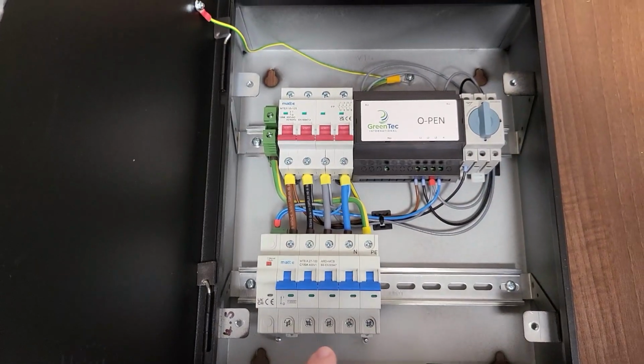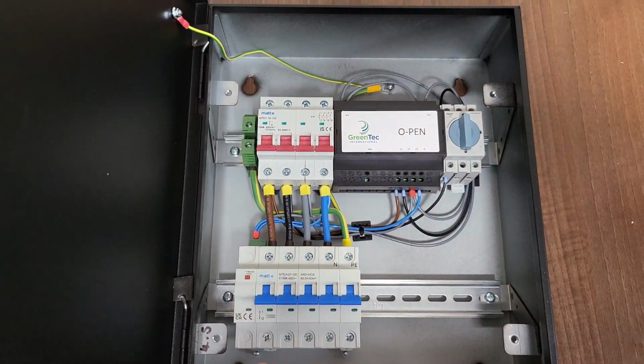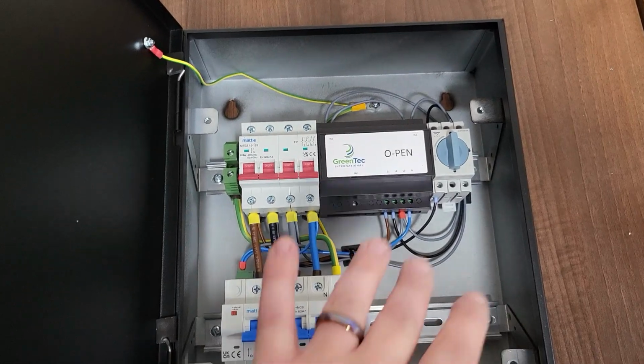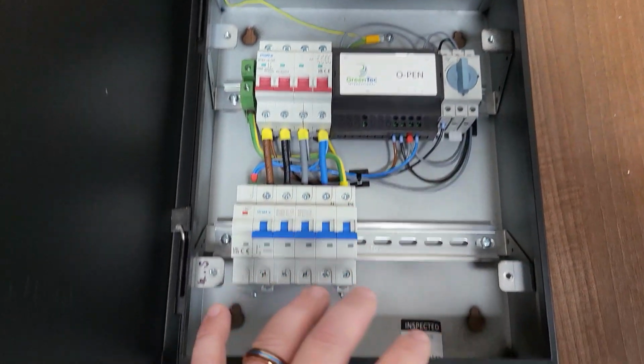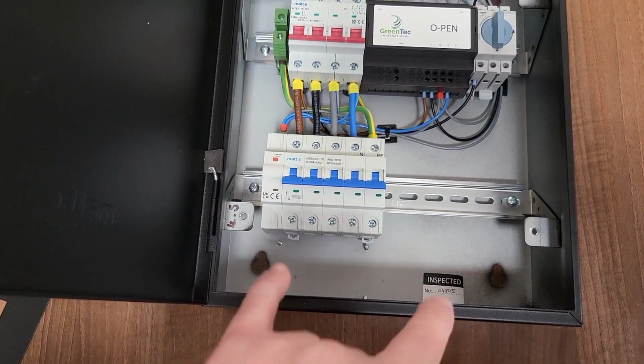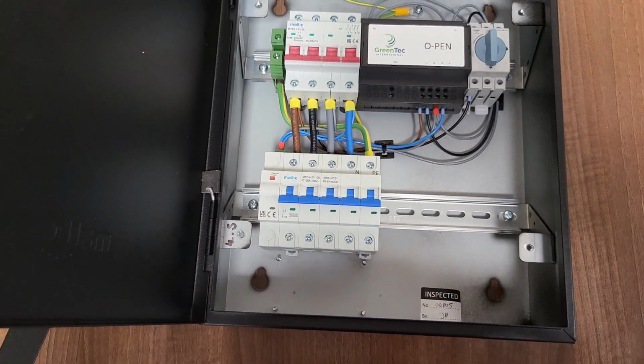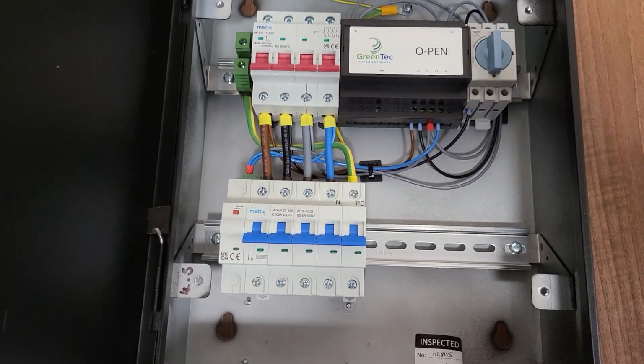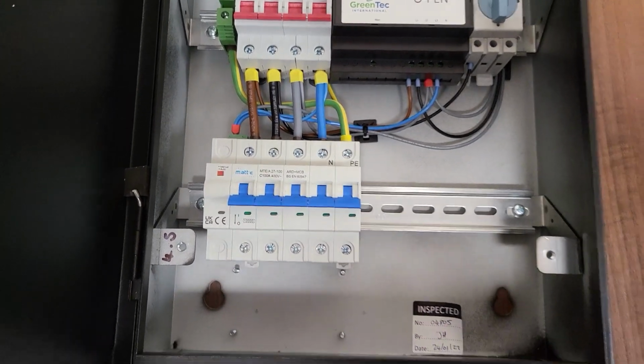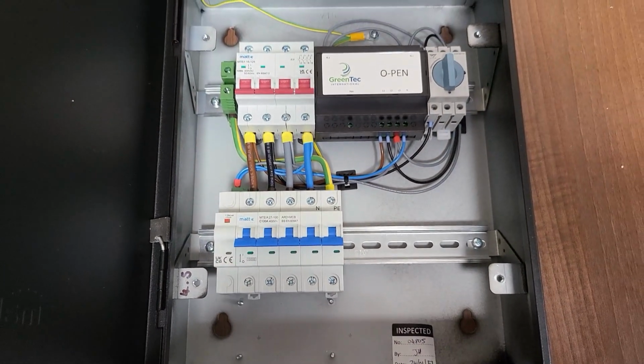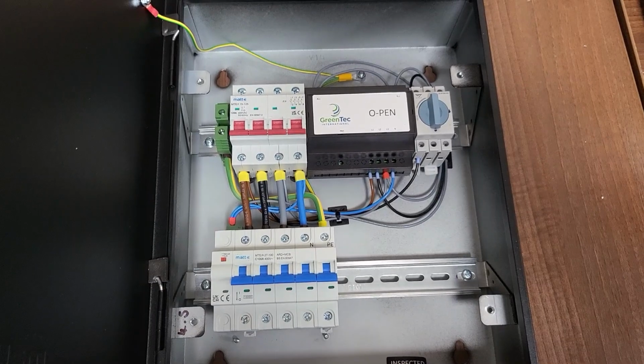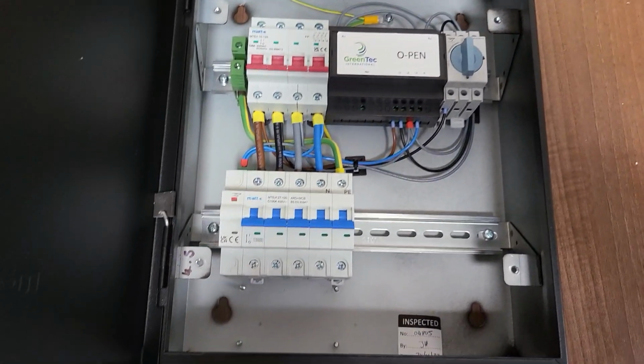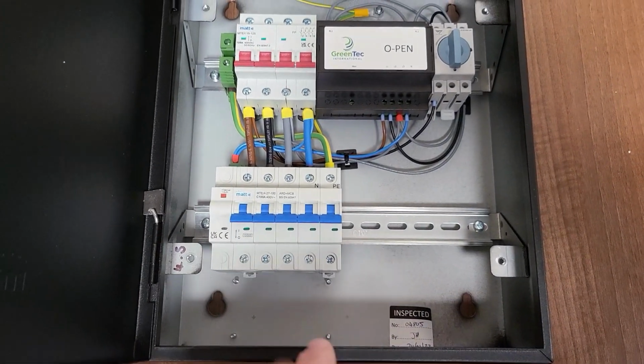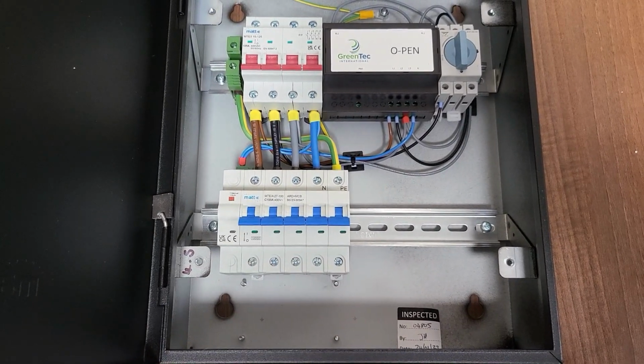So a point of note with this, if you're bringing a supply circuit down in a steel wire armor to this enclosure, that's absolutely fine, but you must remember your outgoing circuit, do not export that earthing to the charge point, because essentially you will bypass what this product is trying to do. So you either need to disconnect your armorings at the end of the charge point, or make sure that you disconnect them as they leave this, use a plastic stuffing gland or such.